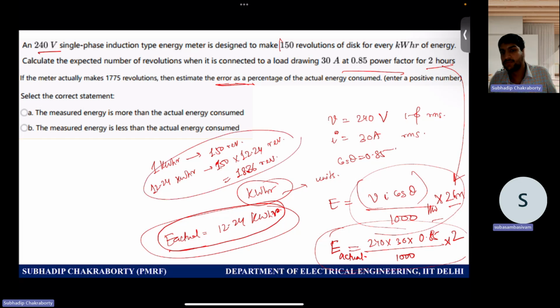So if it would have rotated 1836 times, your actual energy would have been recorded. But due to some errors, it rotated 1775 times. So you need to calculate — a natural phenomenon is that if the energy meter revolves a lower number of times, the energy recorded will be lower than the actual energy. This is trivial, and you can also calculate and check.